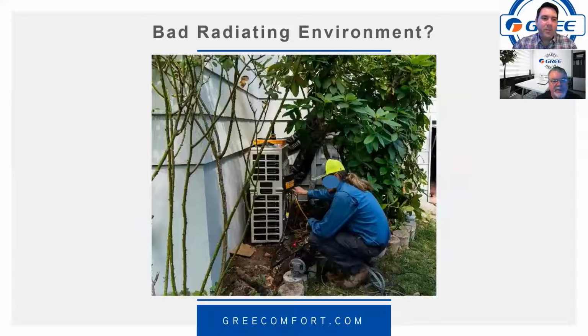And then situations like this as well. What do you see that might be problematic here? I think clearances. Yeah, clearances. This thing is pinned right up next to the house. That's pretty close. I'd be surprised if it wasn't causing an E1. What's the general clearance from the wall? Isn't it about 12 inches? Yeah, it's a foot, which still is not much. It's better than a lot of conventional equipment.